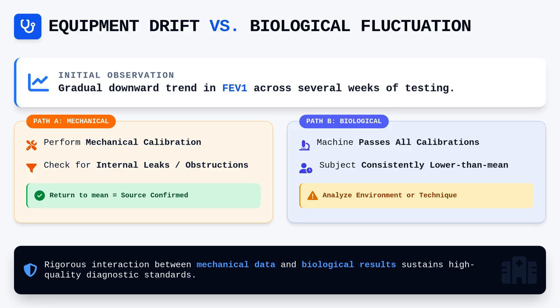In such cases, you should perform a thorough mechanical calibration and potentially check for internal leaks or filter obstructions before continuing diagnostic procedures on patients. If the biological control results return to the mean after a preventative maintenance procedure or a sensor recalibration, you have successfully confirmed the source of the variance. Conversely, if the machine passes all mechanical calibrations but the biological subject consistently produces lower than mean results, you must examine the testing environment or the subject's technique. This rigorous interaction between mechanical data and biological results is what sustains high-quality diagnostic standards in any professional pulmonary function facility.